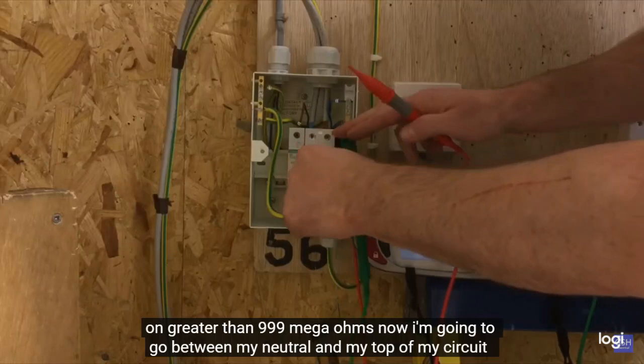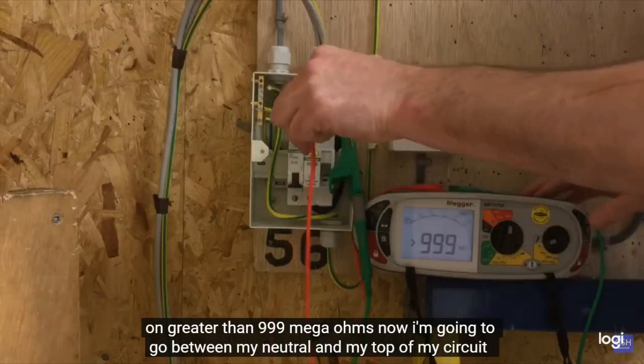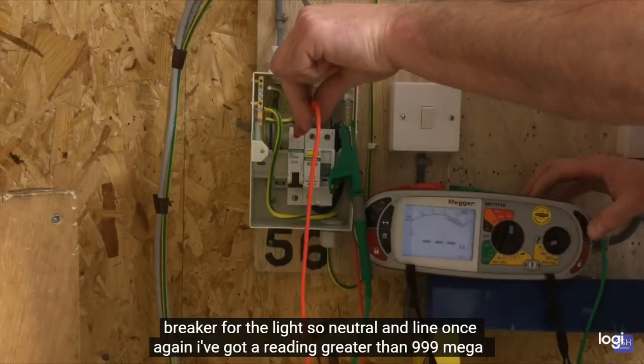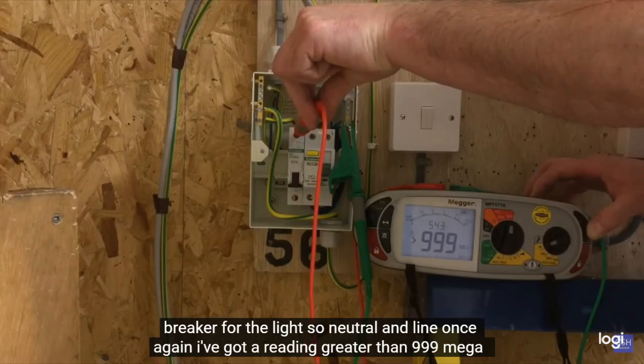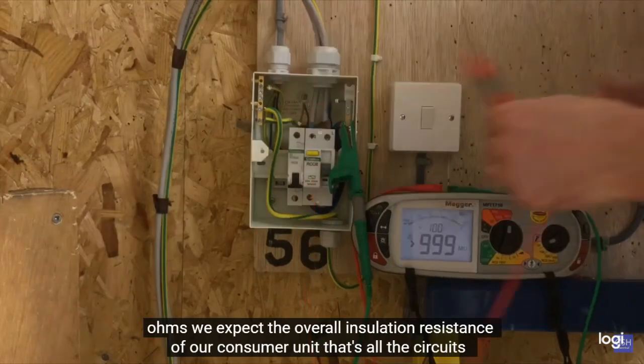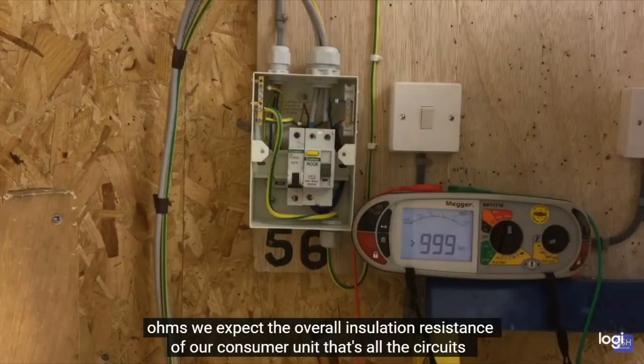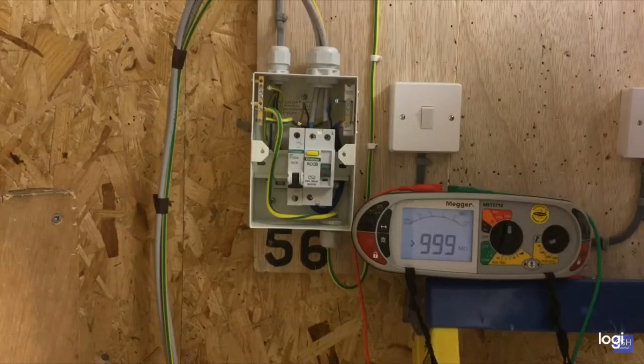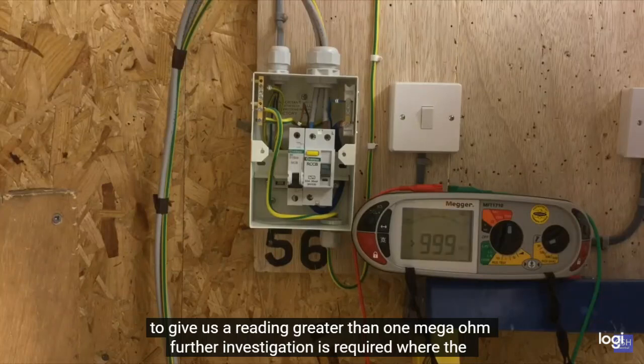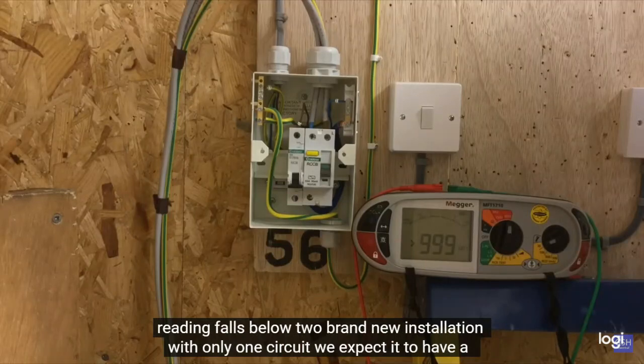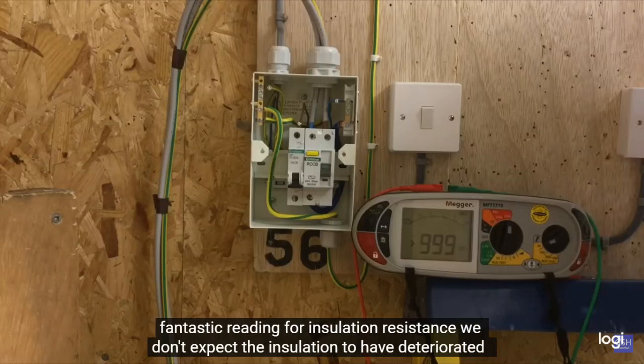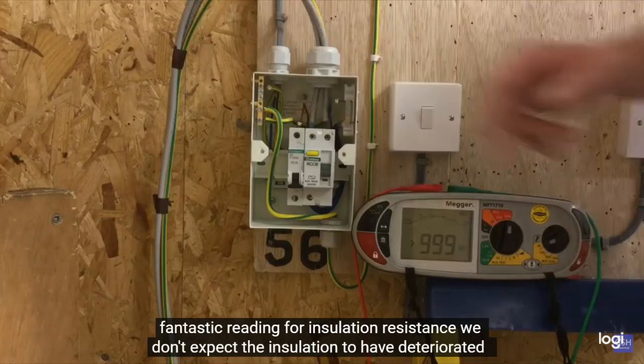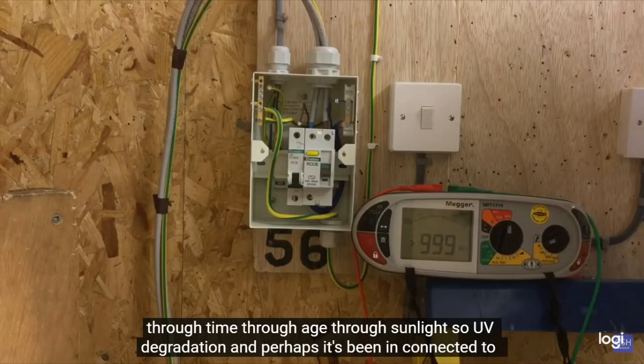We expect the overall insulation resistance of our consumer unit, that's all the circuits, to give us a reading greater than 1 megohm. Further investigation is required where the reading falls below 2. With a training installation with only one circuit, we're expecting to have a fantastic reading for insulation resistance. We don't expect the insulation to have deteriorated through time, through age, through sunlight, so UV degradation. Perhaps it's been connected to something very hot. We don't expect it to have broken down over time. We've got a brand new installation. Our insulation resistance should be fantastically high.